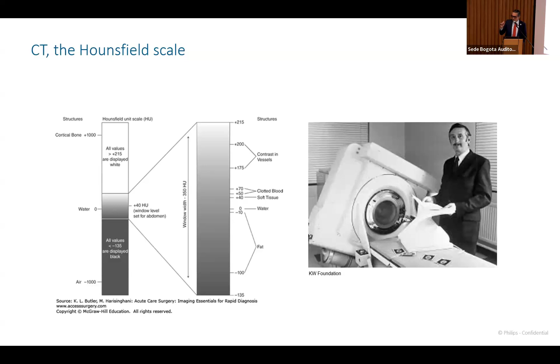So if we compare MR versus CT, CT is winning. Why? Because with every CT image, you can measure a tissue with an exact value, and this value comes from the Hounsfield scale. Of course, every CT machine needs a calibration, needs phantoms with a reference. The reference is water, the center of the Hounsfield unit scale. If the calibration is correct, every pixel that you measure on CT will represent X-ray attenuation.